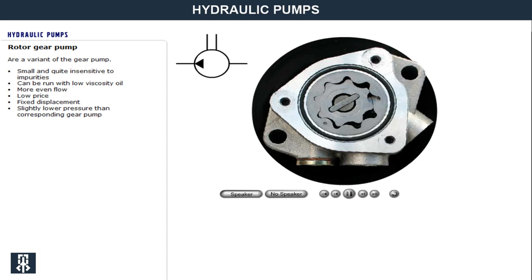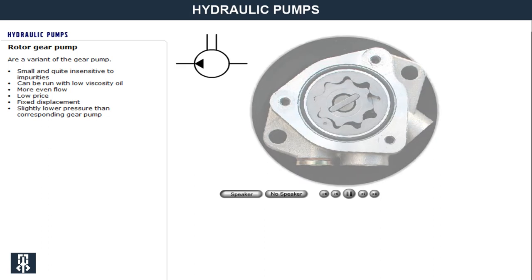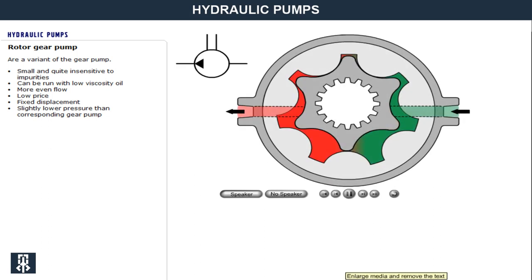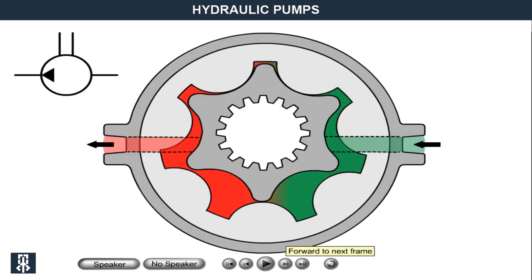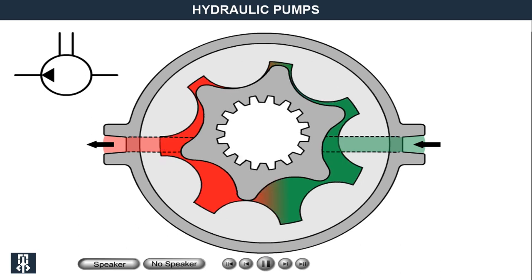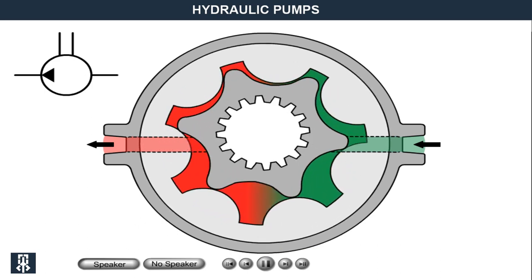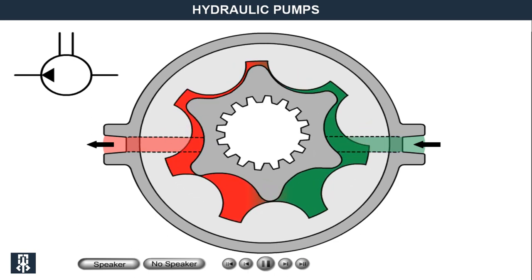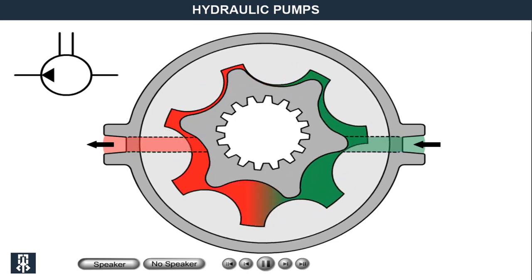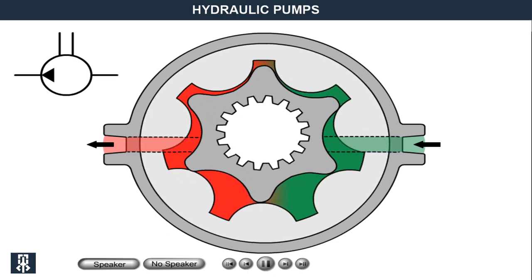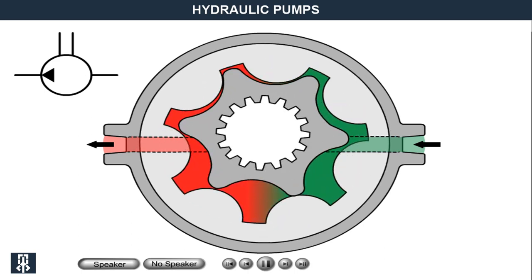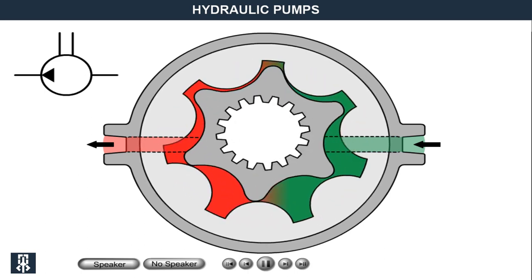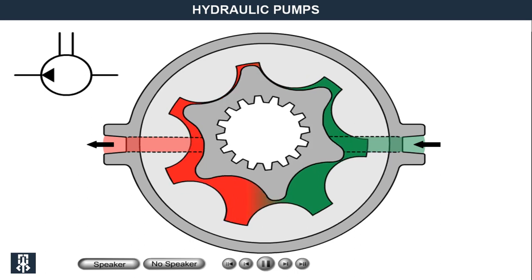For the rotor pump, a variant of the gear pump, the flow's pulsation becomes less distinct. As the rotor in this pump has one tooth less than the internal tooth ring, more than one tooth is never fully engaged with the ring at any one time. Therefore, the oil is not trapped in the same way in the gear engagement as in pumps with gears with outside teeth.